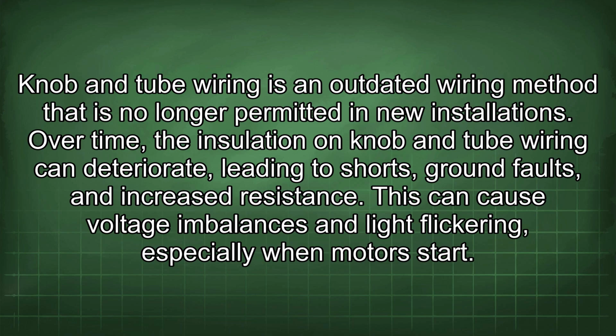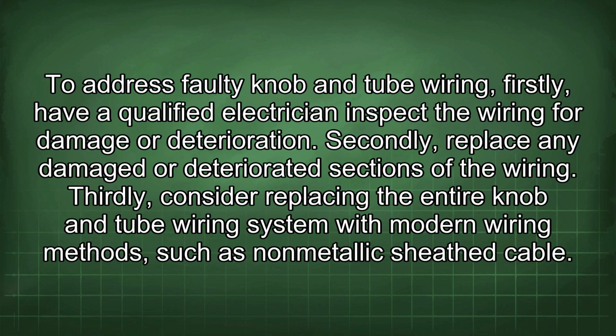This can cause voltage imbalances and light flickering, especially when motors start. To address faulty knob and tube wiring, firstly, have a qualified electrician inspect the wiring for damage or deterioration. Secondly, replace any damaged or deteriorated sections of the wiring. Thirdly, consider replacing the entire knob and tube wiring system with modern wiring methods, such as non-metallic sheath cable.